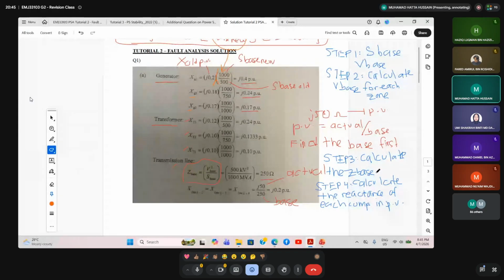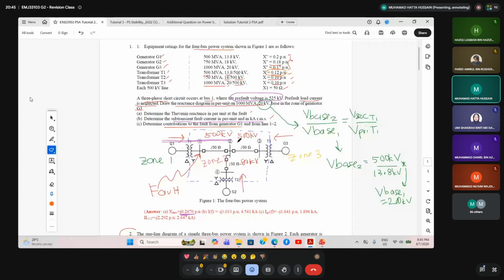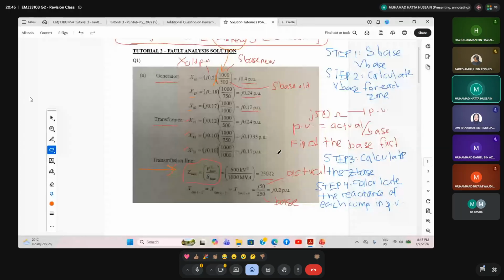calculate the Z base. Okay, this one actually the Z base here. You have to calculate the Z base, which means that the Z base of the transmission line, which is at zone 2 here. So from here, we can get Z base equal to V base squared divided by S base. The V base at zone 2 is actually 500 kV. So 500 kV squared divided by 1000 MVA, which is the S base that we use from step number 1, S base 1000 MVA, which is given in the question. And then we have the answer, 250 ohm.